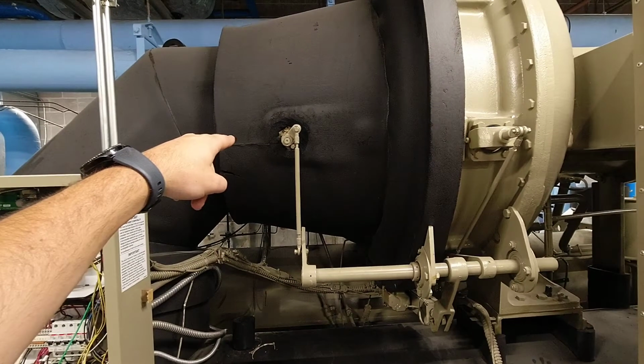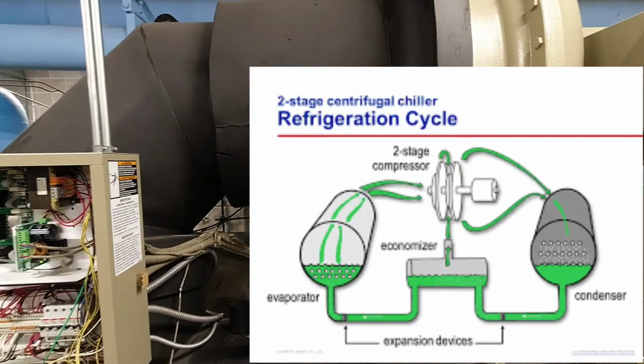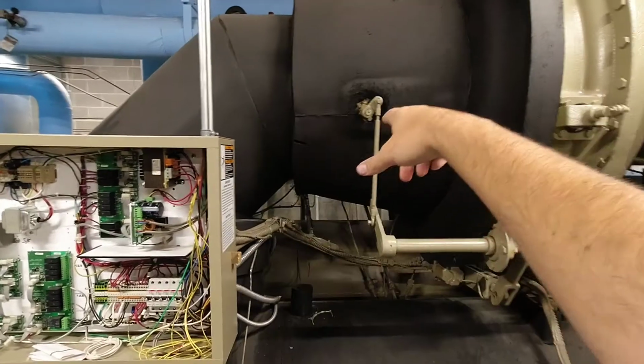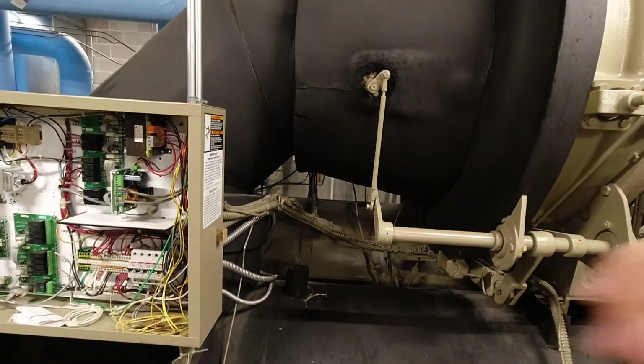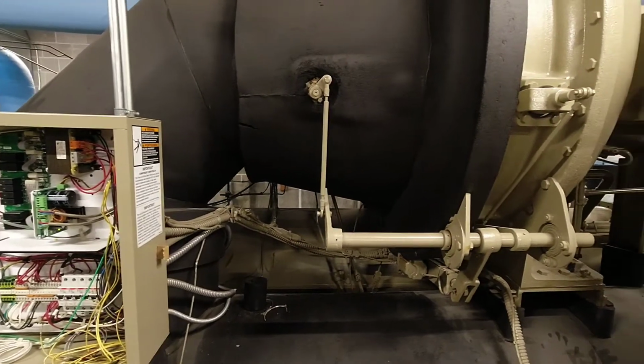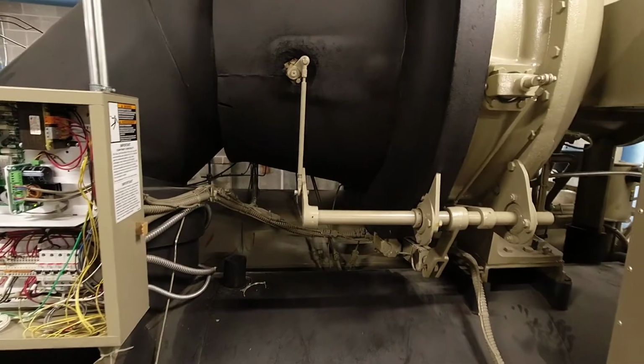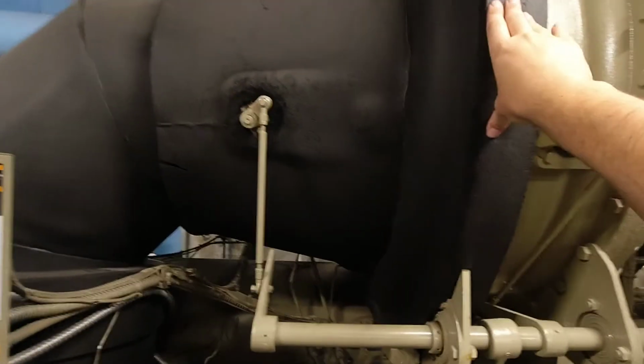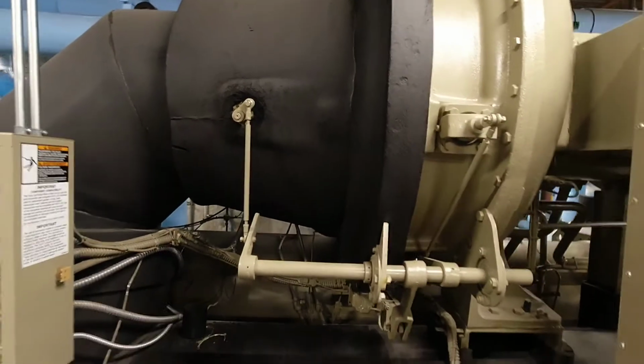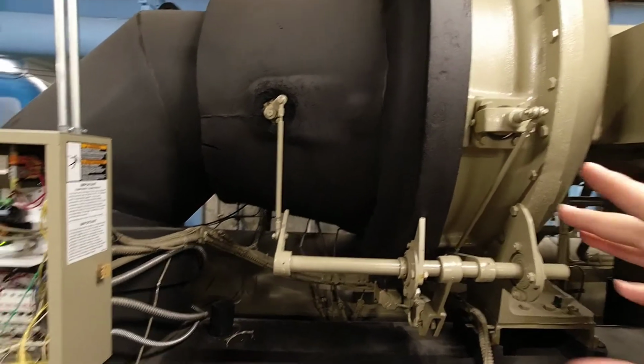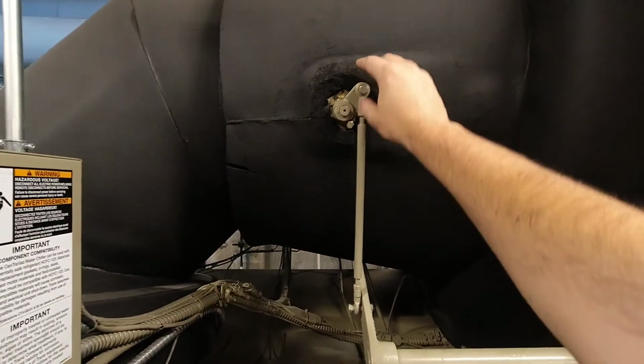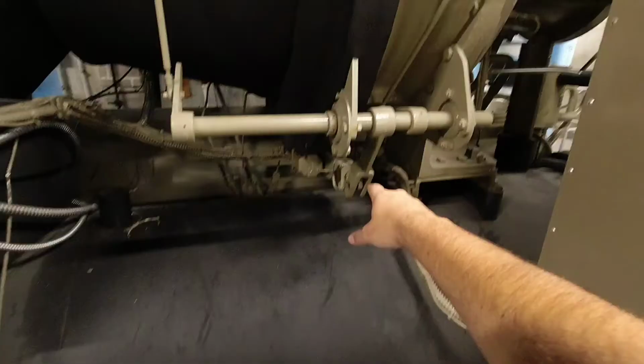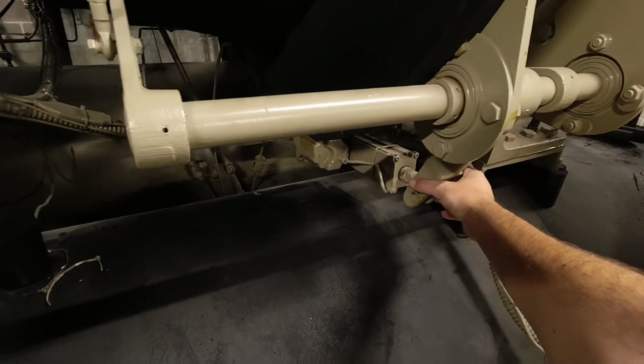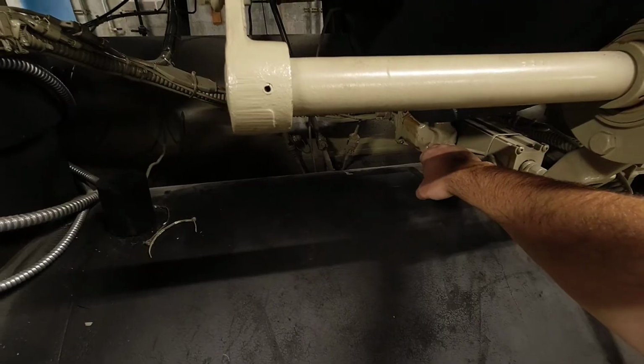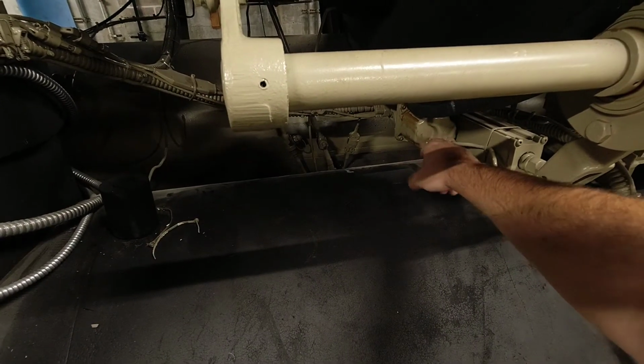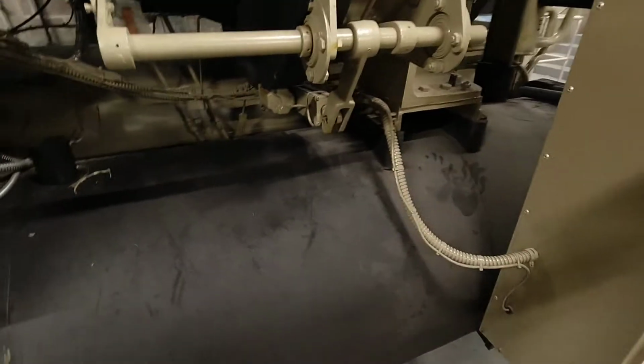Refrigerant's going to come up through the suction and it's going to hit that vane first. So at startup, these vanes have to be at full closed. If they're not, this chiller is not going to start up without tripping on inrush current or something of that nature. You cannot and do not want a load on this motor at startup because it requires so much starting current. So it is looking for these to fully close, which it does with an actuator arm here that opens and closes it. This older series does have a communicating module that runs that arm.